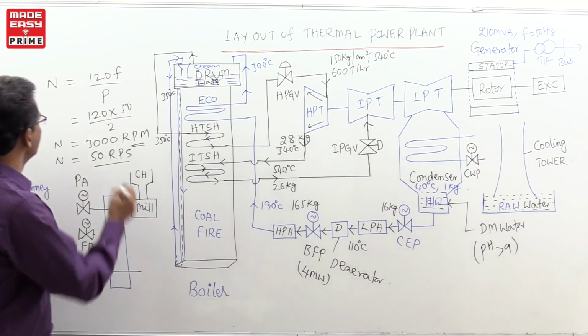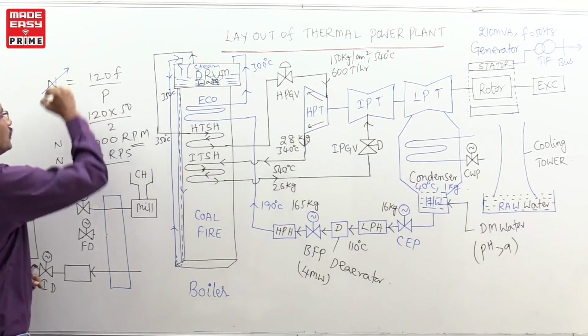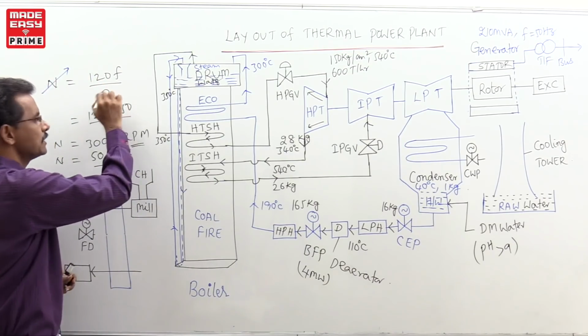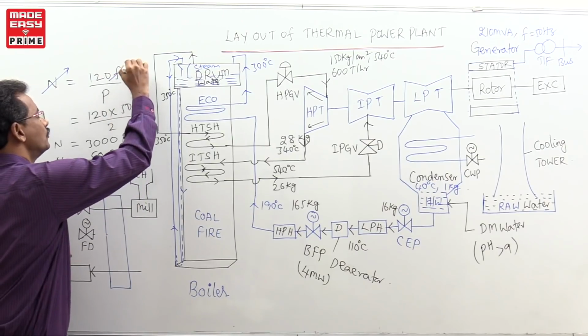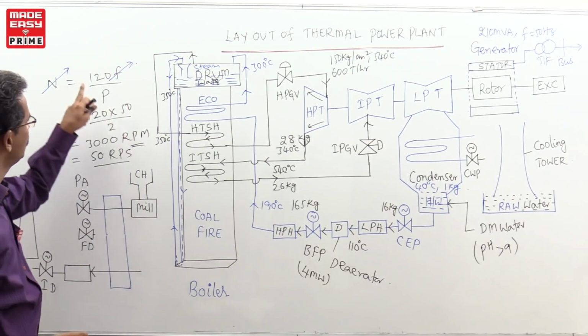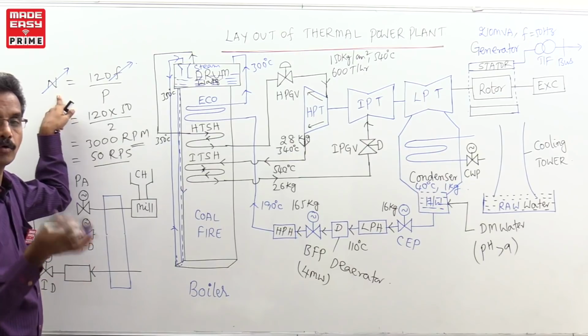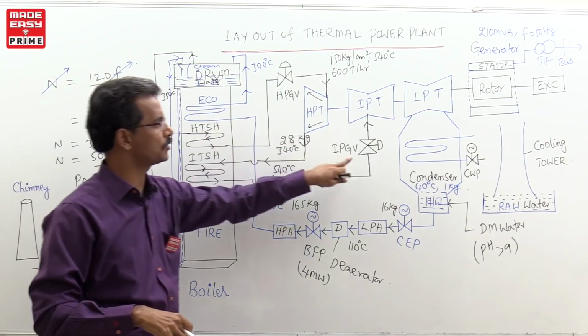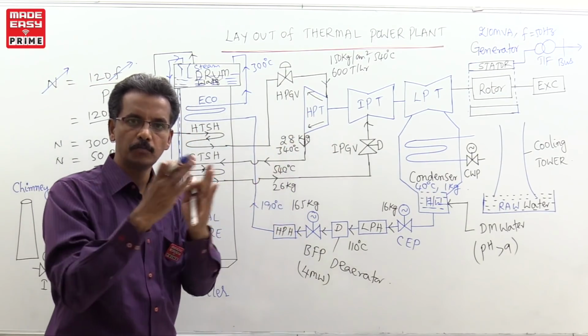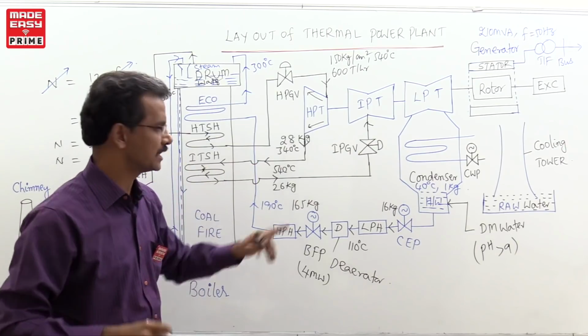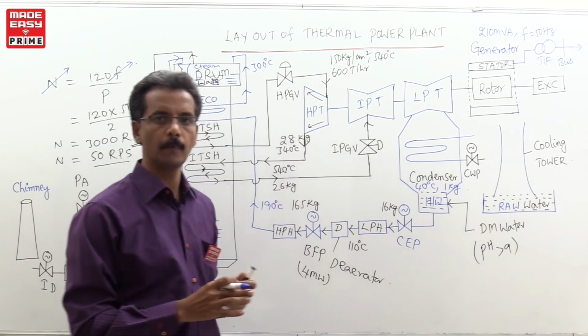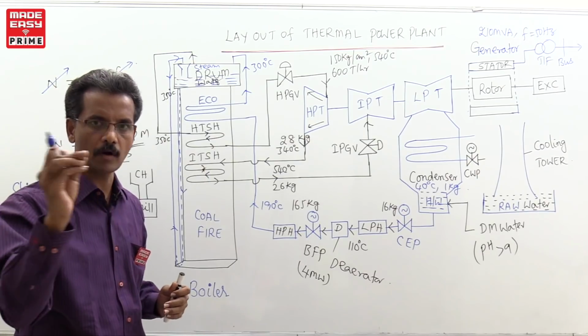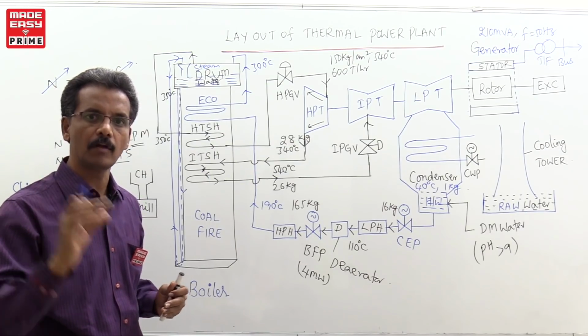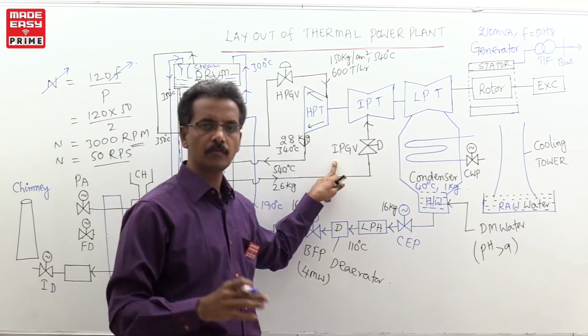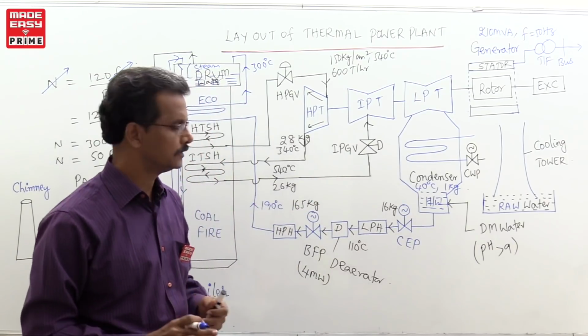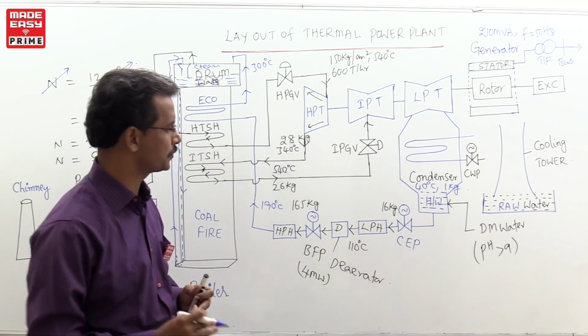So, this is a simple one. If I want to control the speed, since the number of poles P is constant, what will be controlled? Frequency will be controlled. In another way, frequency is controlled by controlling the speed. How to control the speed? The speed is controlled by controlling the governing valve position, which means the steam flow rate is controlled. Right. This is frequency control. This is generally called the speed governing valve control method for frequency control. This is also one of the important questions from the interview point of view.